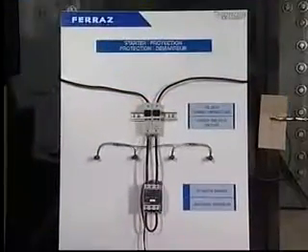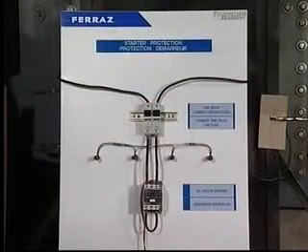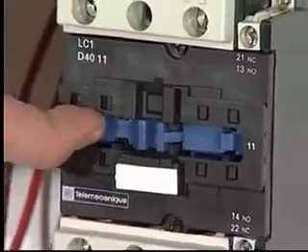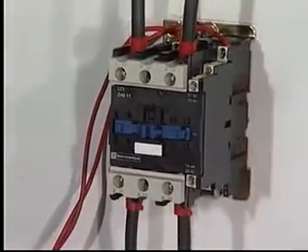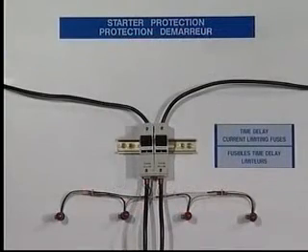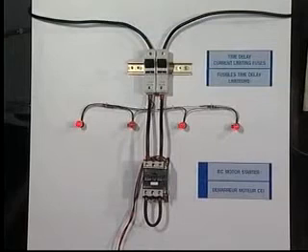The third and last test shows current-limiting Class J time delay fuses. The test is identical to the prior tests, with a new starter once again used. The contacts are fully functional before the test. With all of the preceding fuse tests offering such exceptional but uneventful protection, we decided to add lights to this test, simply to confirm that the circuit indeed experienced a fault current.